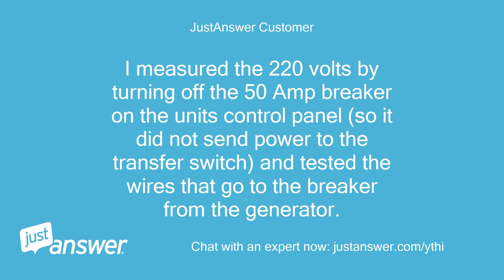I measured the 220 volts by turning off the 50 amp breaker on the unit's control panel, so it did not send power to the transfer switch, and tested the wires that go to the breaker from the generator. As for the oil pressure switch, I just pulled the wire off and let it hang in the air. FC2 is the code for oil pressure, and I did not get that code.